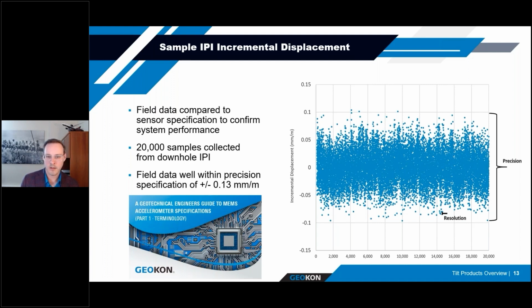When you talk about the actual performance of a product in the field, you're talking about system performance, not sensor performance. So what you see here is a collection of 20,000 readings for an IPI where we deemed there to be no movement. So we're really looking at the precision of this particular sensor across 20,000 samples. The sensor precision that we've put on our specification sheet is plus or minus 0.13 millimeters per meter, and that's at a 99% confidence interval.